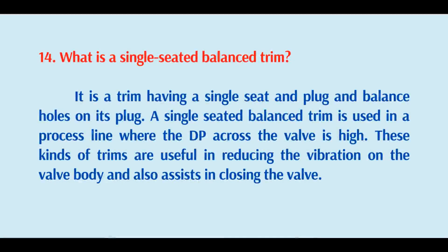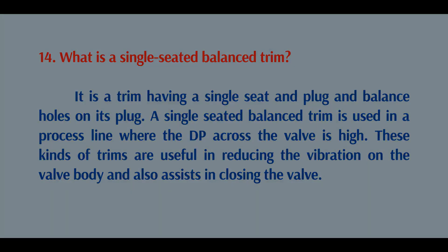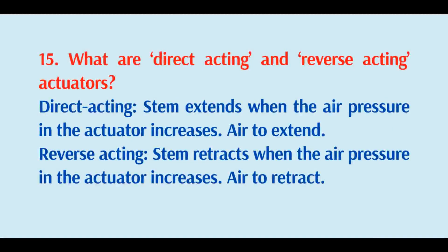What is a single seated balance trim? It is a trim having a single seat and plug with balance holes on the plug. A single seated balance trim is used in a process line where the differential pressure across the valve is high. These kinds of trims are useful in reducing vibration on the valve body and also assist in closing the valve.